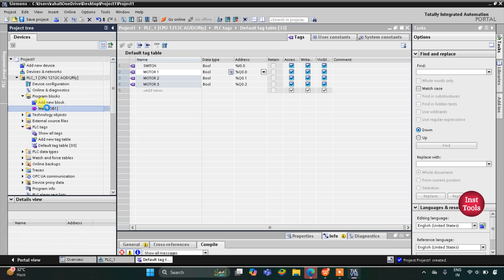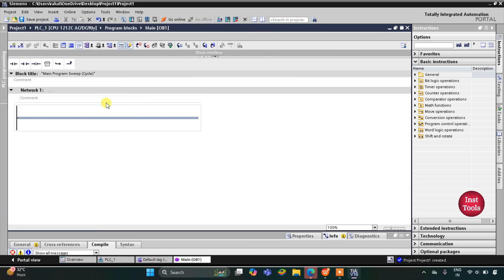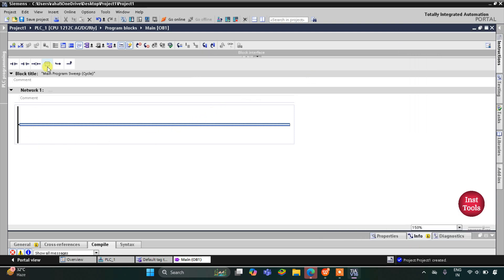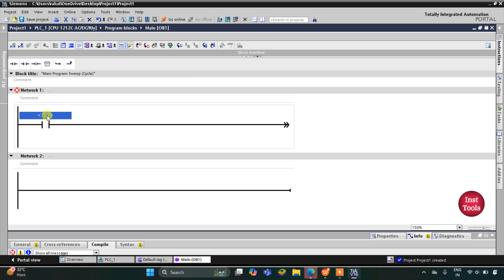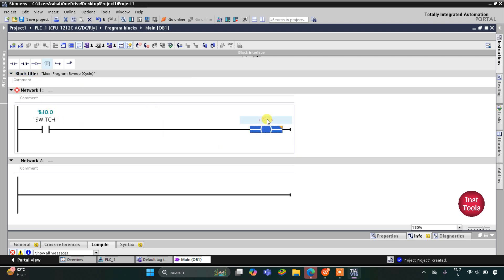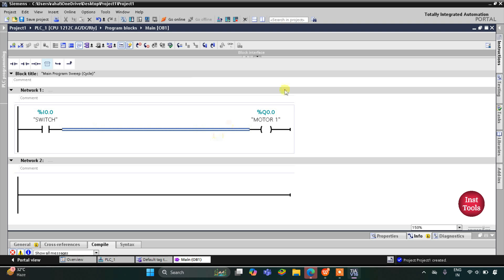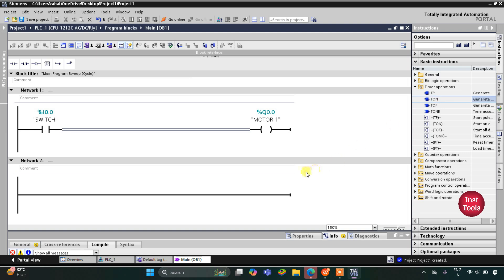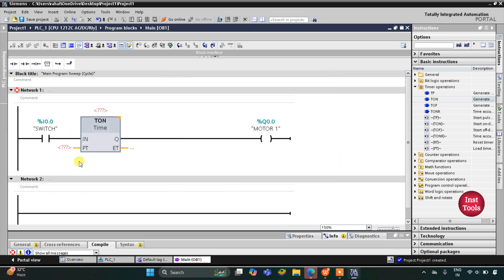Then I will go to Program Blocks and then Main OB1, where we will be drawing the ladder diagram. I will minimize this and zoom in. Here I will insert a normally open contact for Switch — I will write S and select Switch from the list. Then I will add a coil for Motor 1 and select Motor 1. Motor 1 will turn on after 5 seconds, so I will insert a TON timer operation.